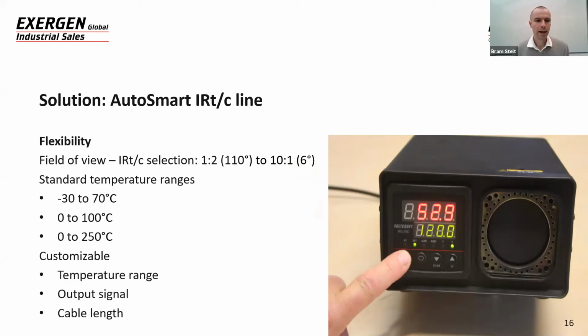We offer this by allowing any IRTC to be connected to the AutoSmart transmitter. So you can select an IRTC on field of view mostly, could also be size, of course. But the IRTCs that can be connected to the AutoSmart vary in field of view from 1 to 2, the micro IRTC, which is approximately 110 degrees, a very wide field of view, to a more focused 10 to 1 field of view, or 6 degrees.